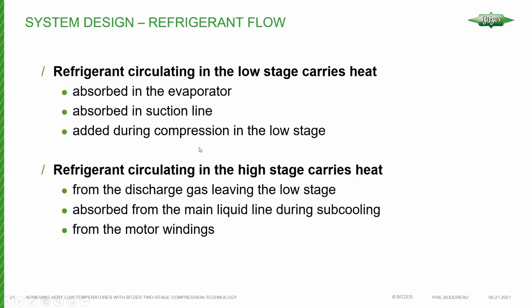So refrigerant circulating in the low stage carries heat that's, of course, absorbed in the evaporator, any heat that's picked up from the suction line, and any heat during the compression process in the low stage. So this will be your heat of compression, which every compressor has. Refrigerant circulating in the high stage, on the other hand, carries the heat from the discharge gas leaving the low stage, okay? Because these two internal compressors are in series. So everything that leaves the low stage now ends up in the suction of the high stage circuit.